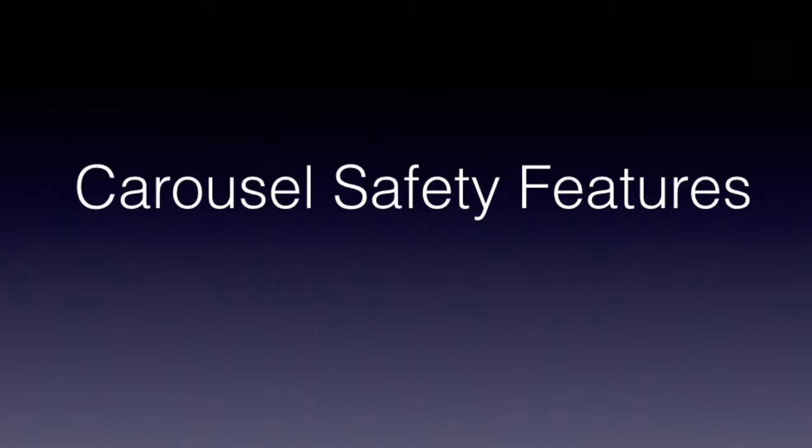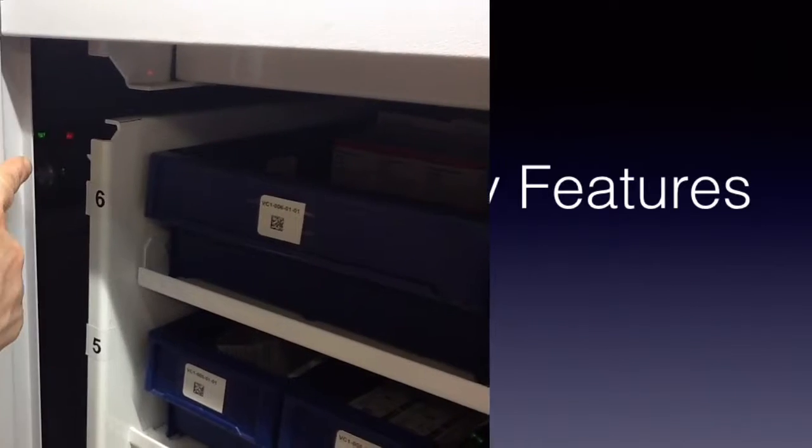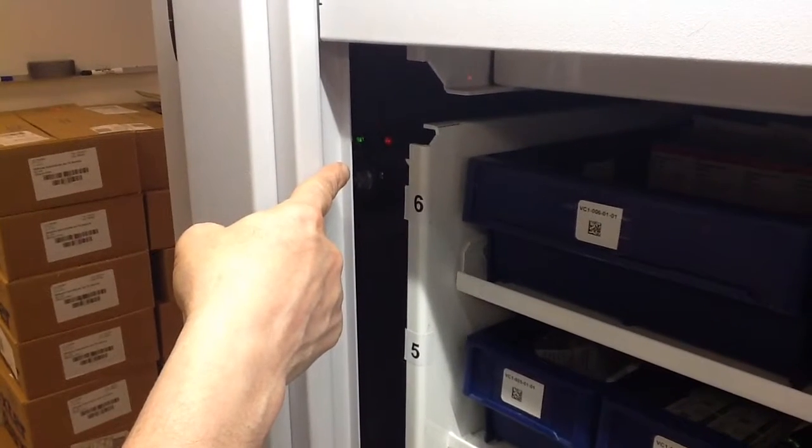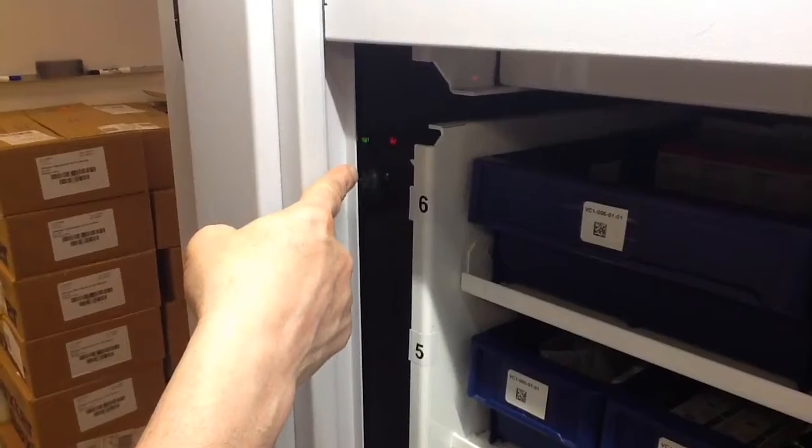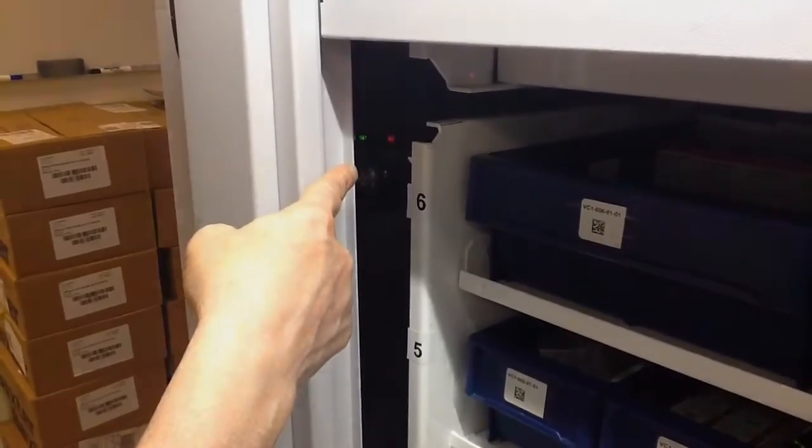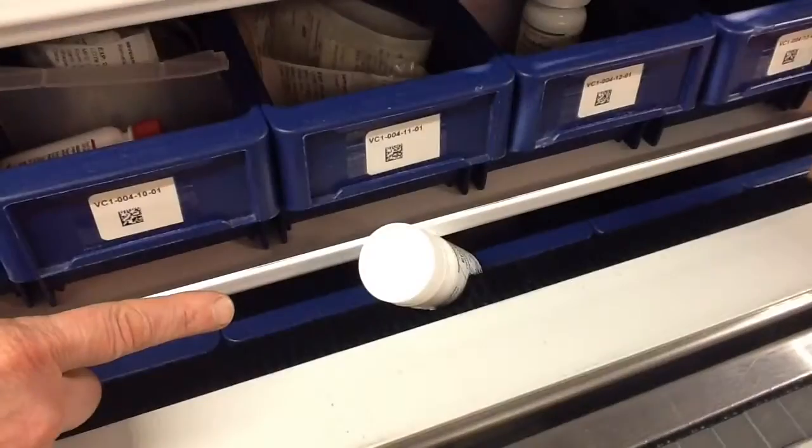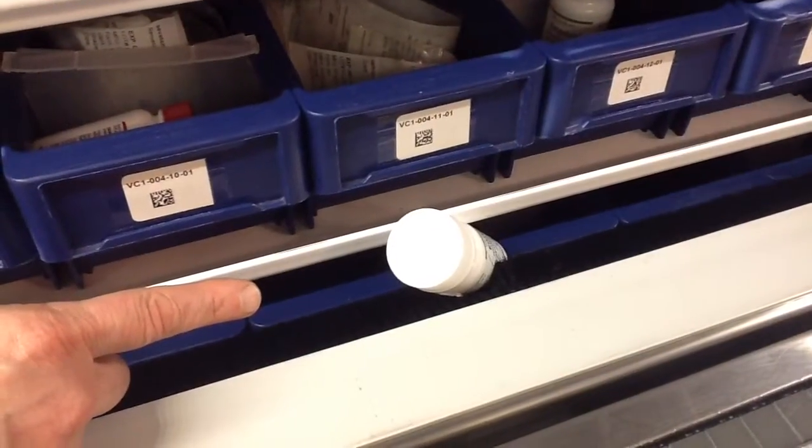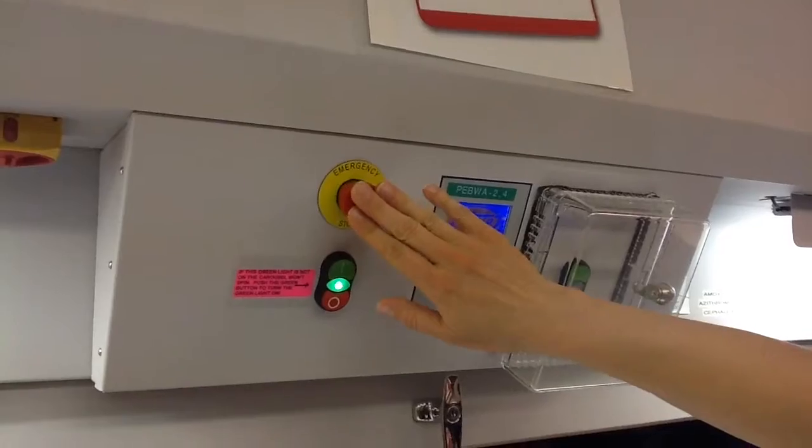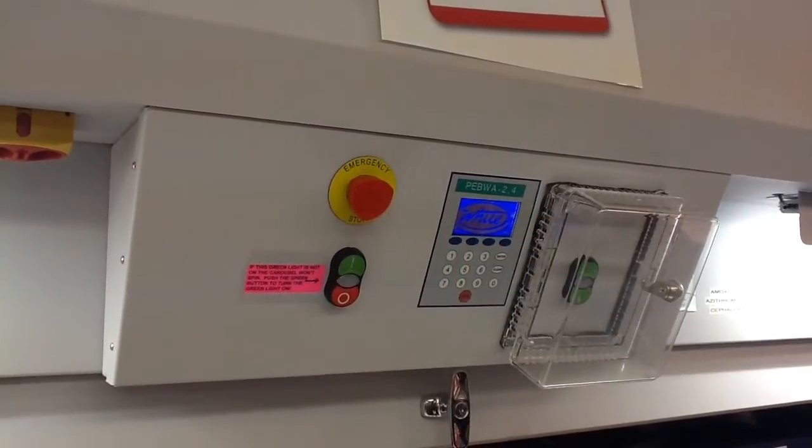Next, let's discuss safety features. The carousel will stop spinning when one of the following occurs: the light beam is broken by an obstruction such as a bin or product sticking out, something brushes up against the bristles, or emergency stop button is pushed.